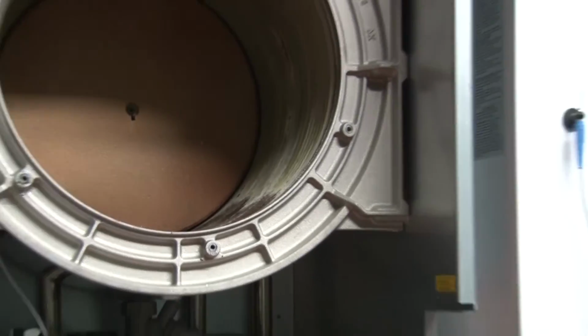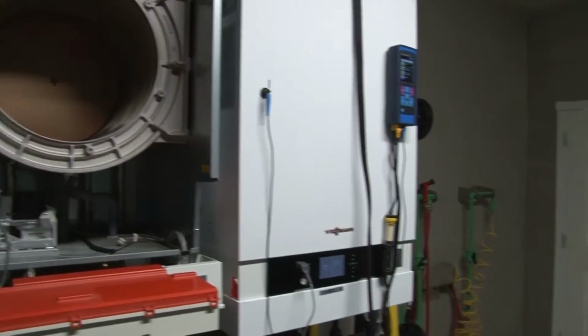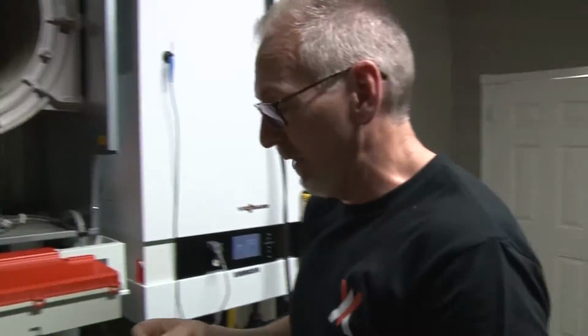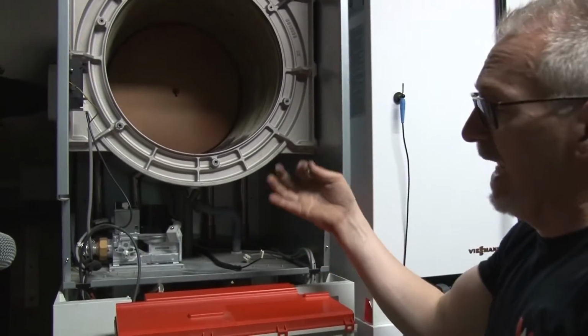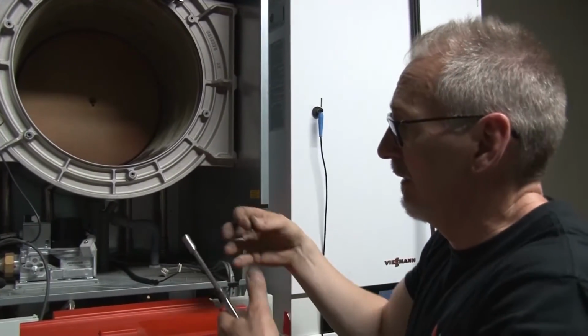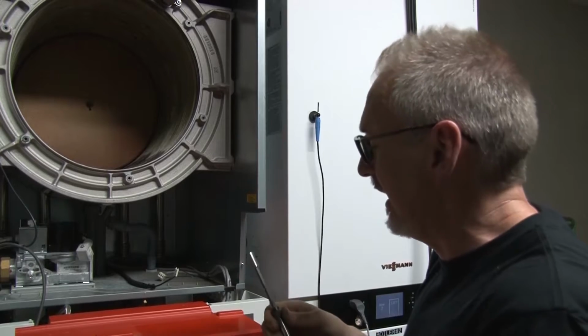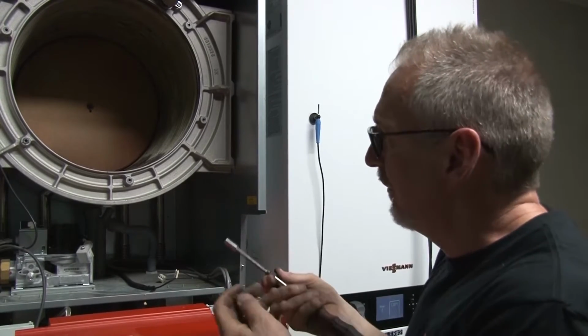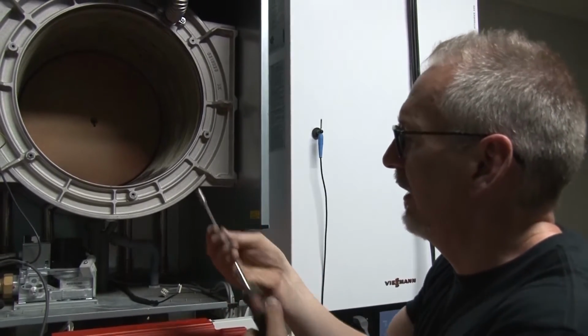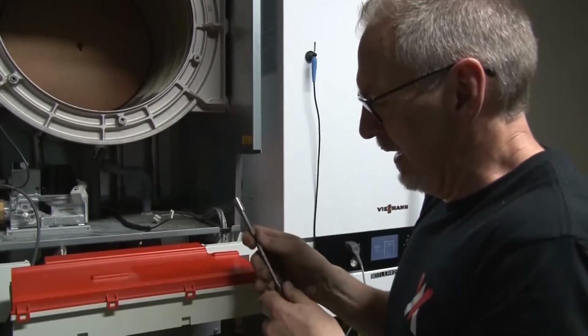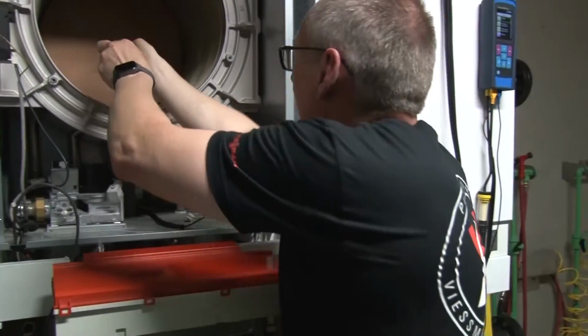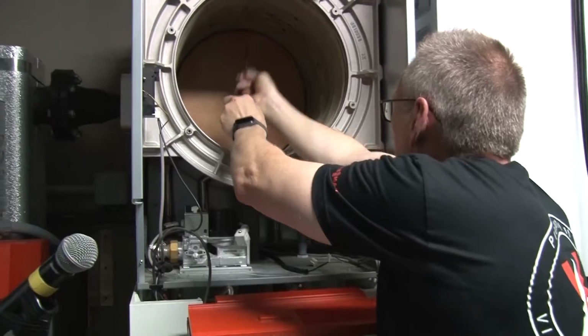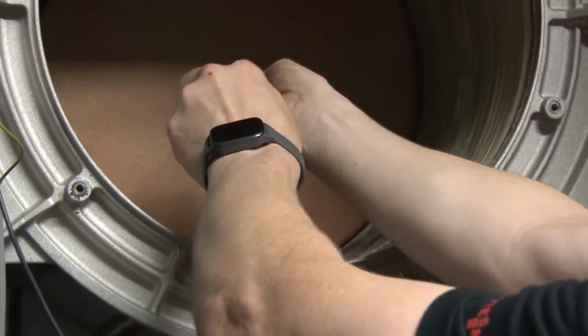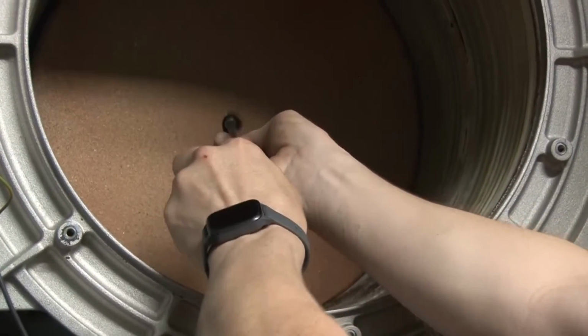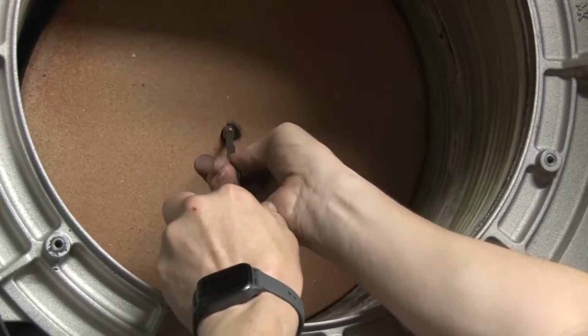You want to make sure, in some of the bigger commercial boilers we're going to be working with later today, that we don't have anything on the side of the boiler that's going to fall inside there. We might lose that in the heat exchanger. And now that I've pulled that out, I can take my little tool here, extend it out a bit, and grab that refractory and pull it ahead a little bit so that I can capture it.